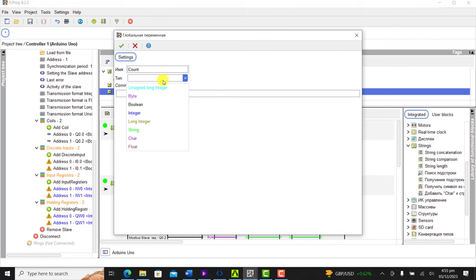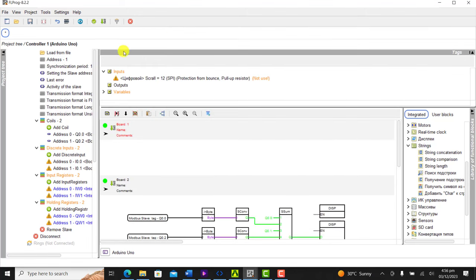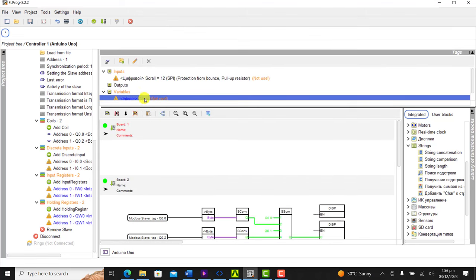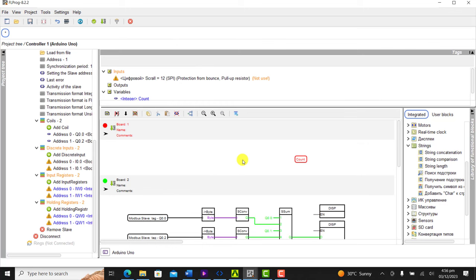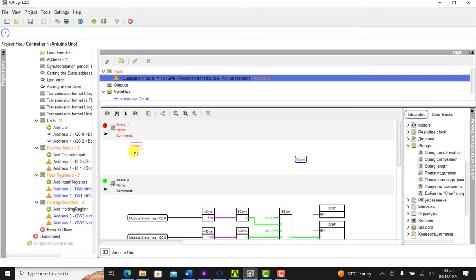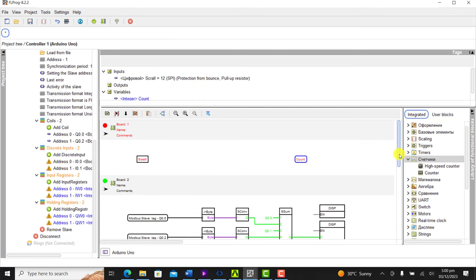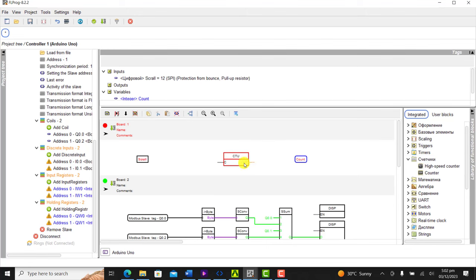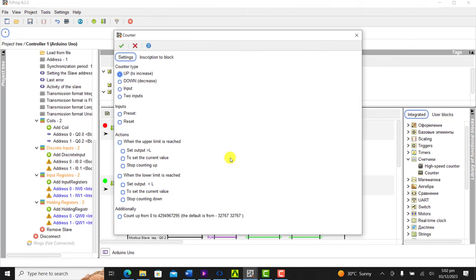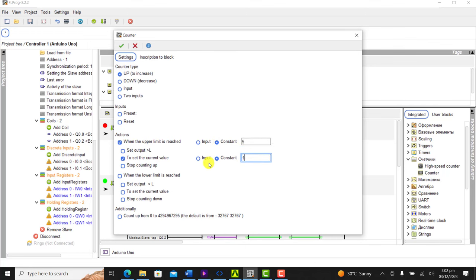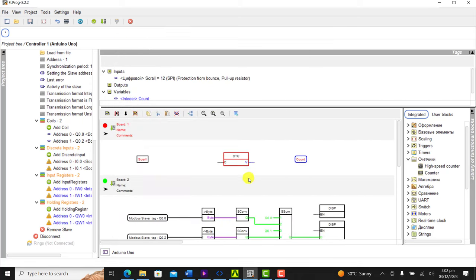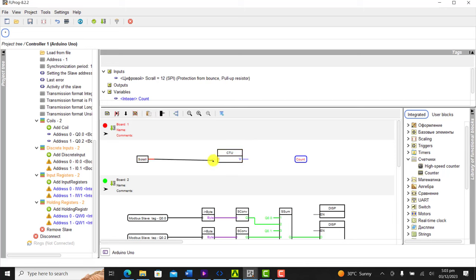We now need to create a counter variable which is an integer variable. So we bring the count variable and then the scroll button as well. We select a counter and configure it as an up counter with a maximum count of 5, and then start from 1 again. We click OK, position it correctly, and then wire the scroll to the input and then the output to our count variable.